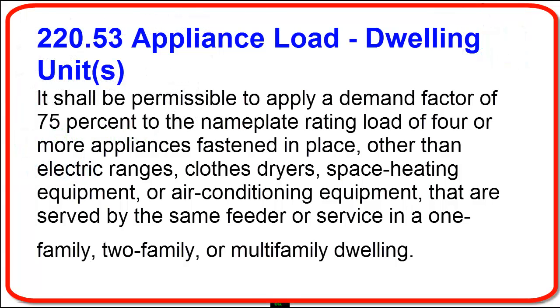Now, how about our fixed appliances? In 220.53, we also find that it's permissible to apply a demand factor of 75% to the nameplate rating load of four or more appliances that are fastened in place. This does not include ranges, clothes dryers, space heating equipment, or air conditioning equipment.